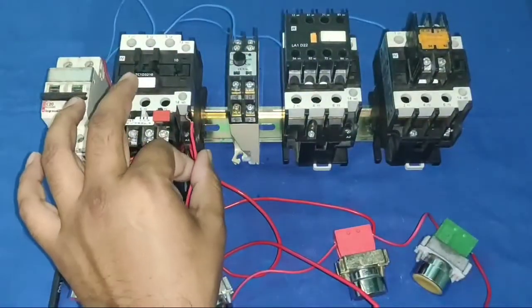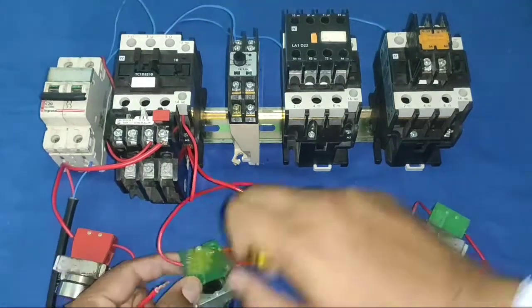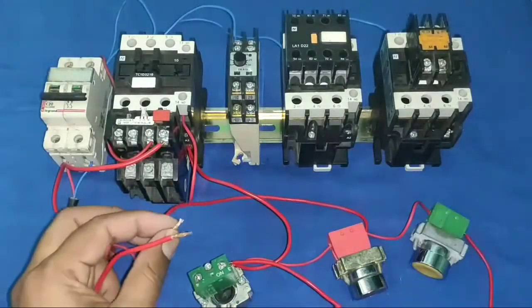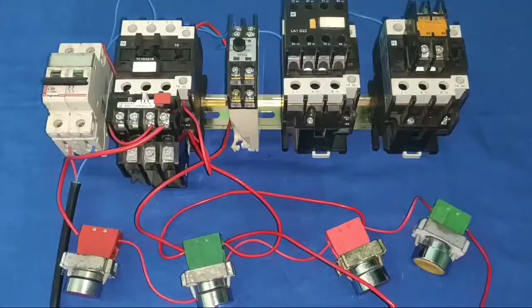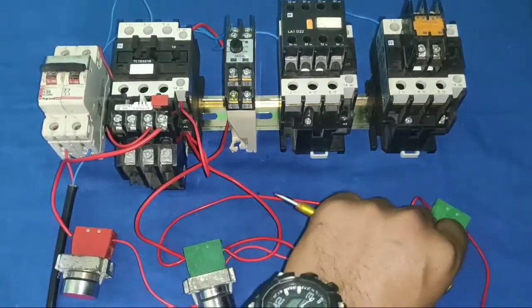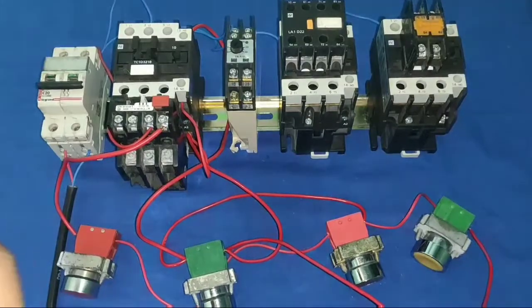Now we expand the DOL starter to a star delta starter. We take holding supply from the NO element input side and connect one wire to the contactor NO terminal. Our DOL starter control wiring is now complete — you can start and stop from either push button location. Now let's implement this into the star delta starter.